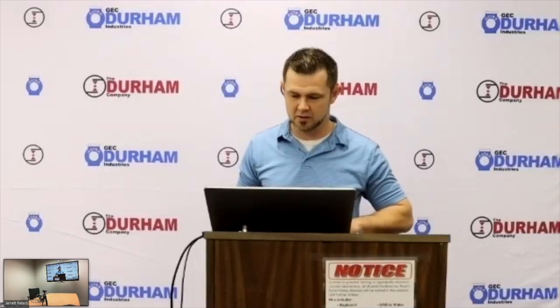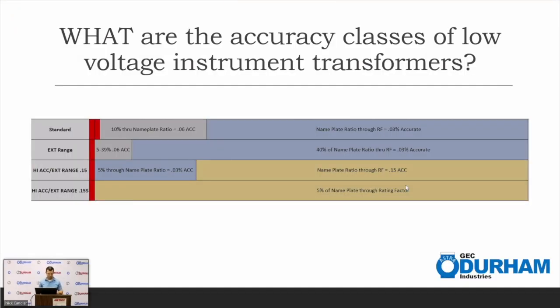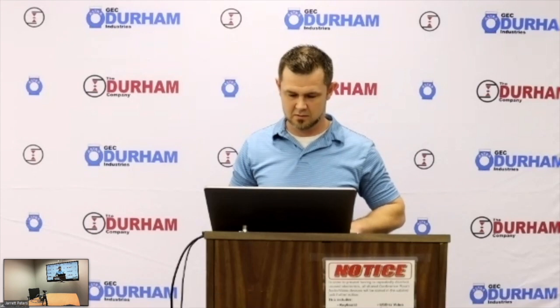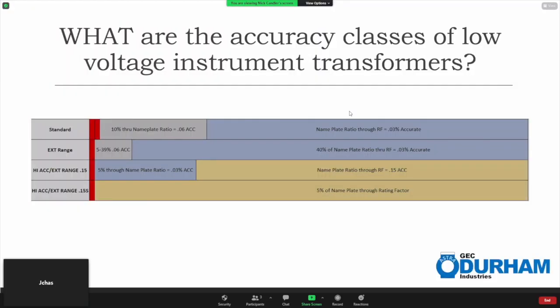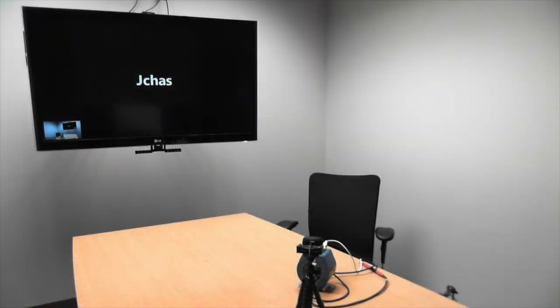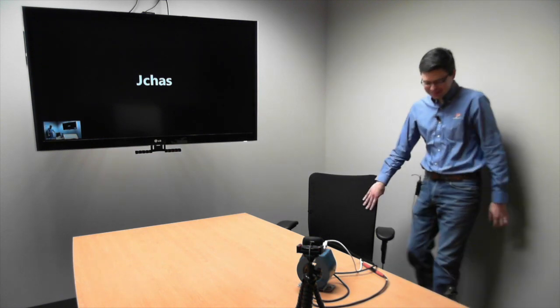Yeah, good point. Those are all important to highlight. This is why I was so excited about this particular CT, because I've never been able to go down below 10% and get a good reading. So super excited about it. But those who have hung around for the presentations we had in the past, we do talk a lot about the benefits of the CT itself. Sometimes we'll talk about the accuracy class and that rating factor. And I know Nick will talk a little bit in the presentation about rating factor, why that's important, because rating factor can affect your accuracy as the temperature increases. So while we're waiting for Nick to come back, we'll switch over to the on-site demo.